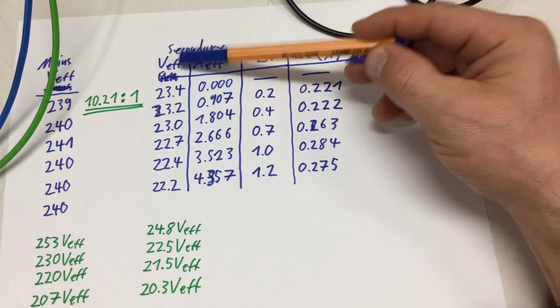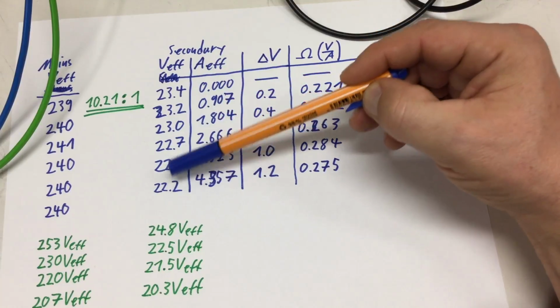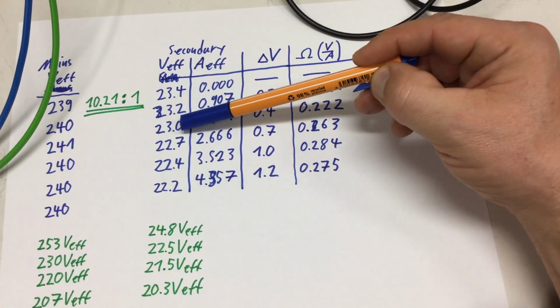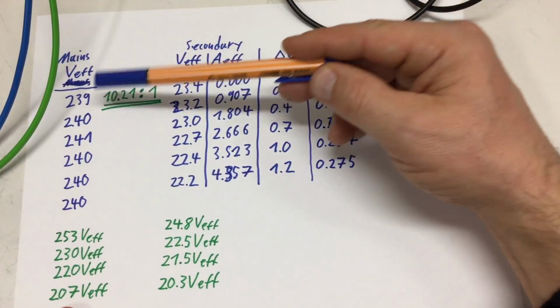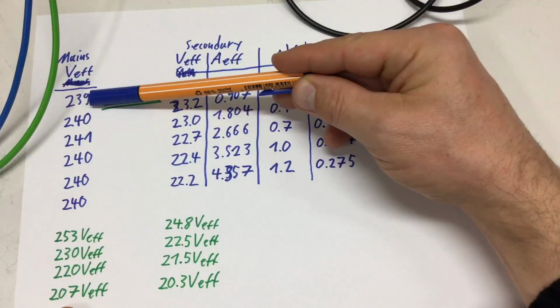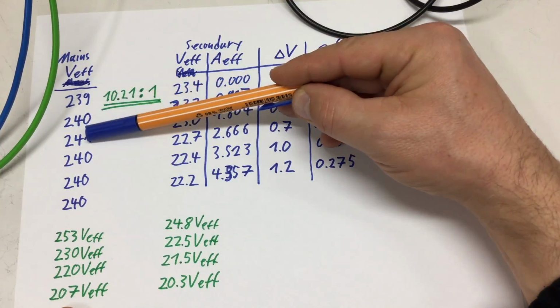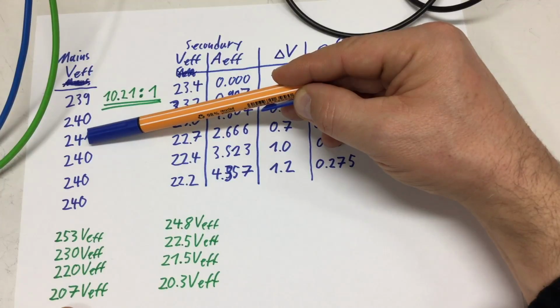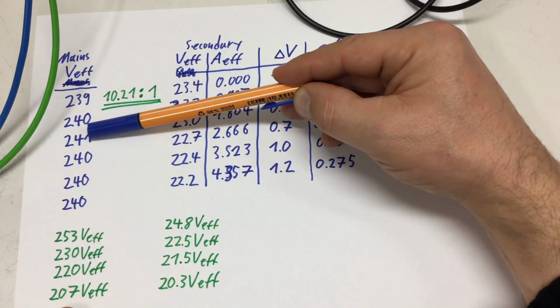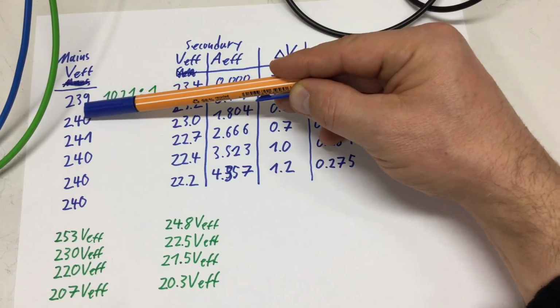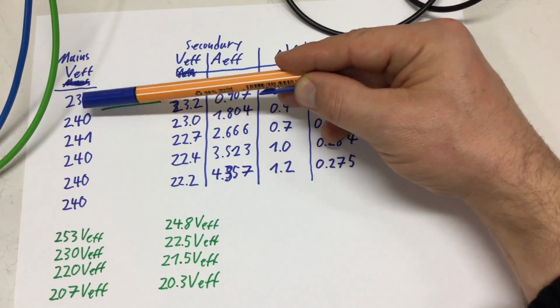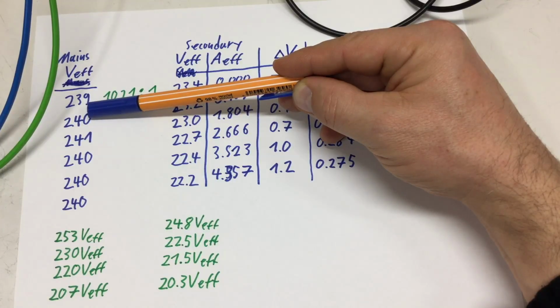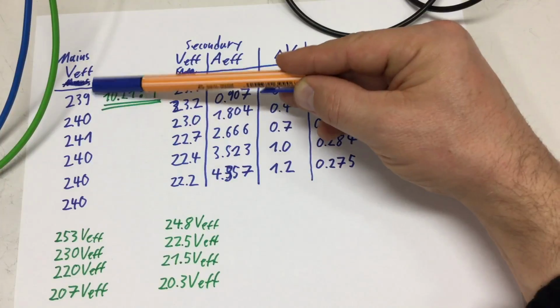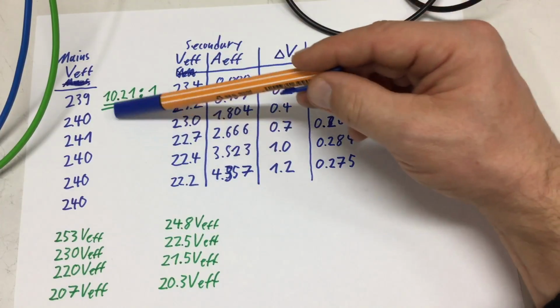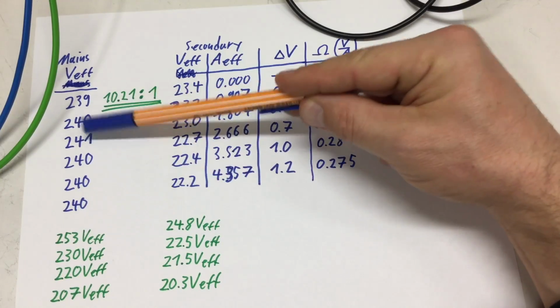So each time I measured, I increased the load, I measured the effective output voltage, and also had a look at the mains voltage. Because the mains voltage is not even 0.5% off. I mean, 240 volts, 10% is 24 volts, 1% is 2.4 volts, so less than half a percent, and we're not measuring that accurately, so I will not make any adjustment for that variation.